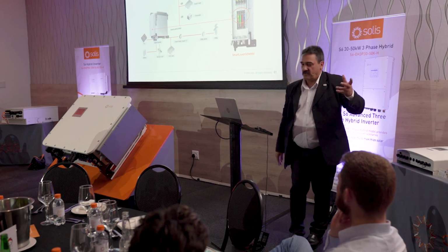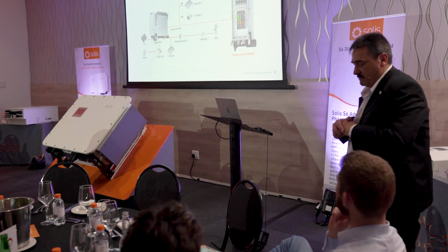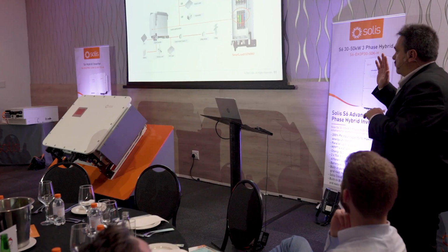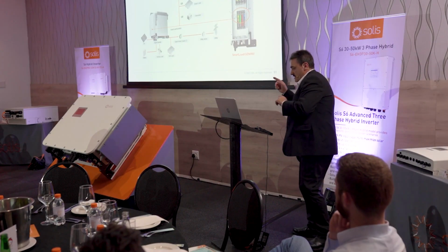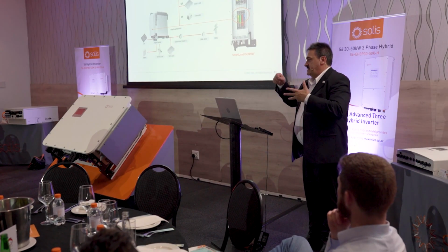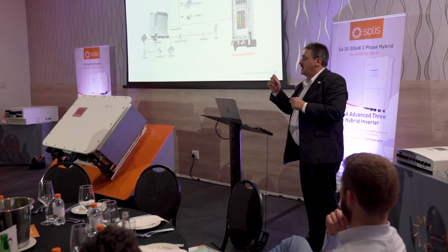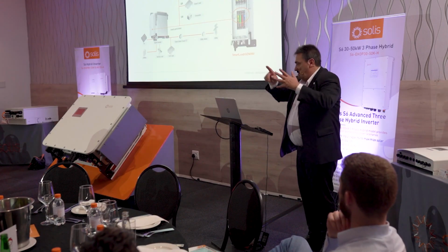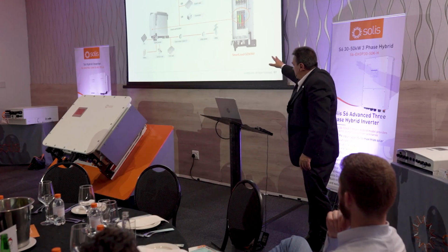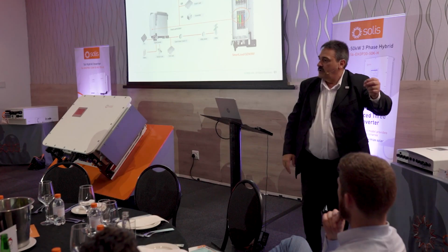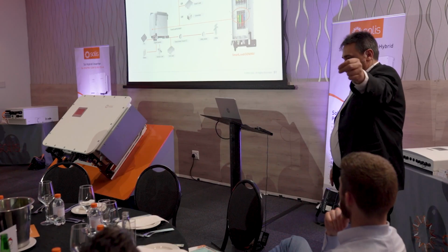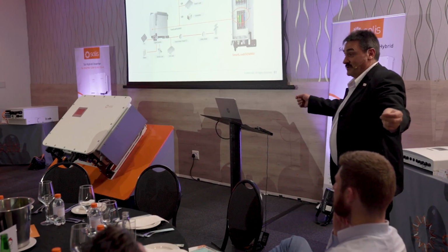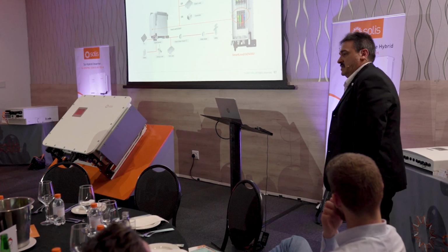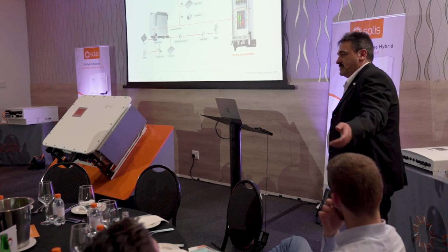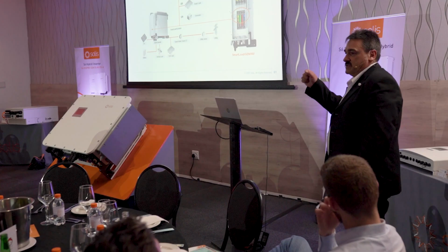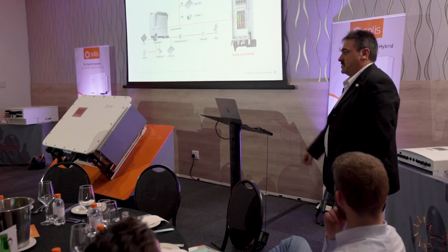So what we generally recommend, this is a little bit off the topic, but it will help a lot. In your home run, you don't even have to do the math these days. You've got online calculators, like a gazillion of them. You just put in the length, the current, and the voltage that you're going to carry it at. It will give you a voltage drop percentage. All I'm asking is that you keep the voltage drop under 1%. Not 5% or 8% like in the house, where people don't care. PV systems don't like high voltage drops.